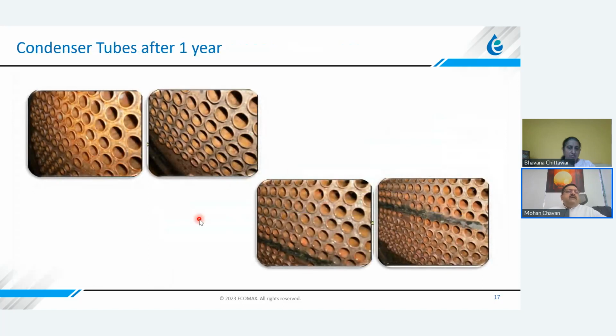So based on our experience, we also opened the condenser tubes after 1 year, 2 years, 4 years at various sites. And we found that the condenser tubes are quite clean here. And that's where the condenser approach is maintained, okay? And it has improved energy efficiency substantially in the water-cooled chillers.